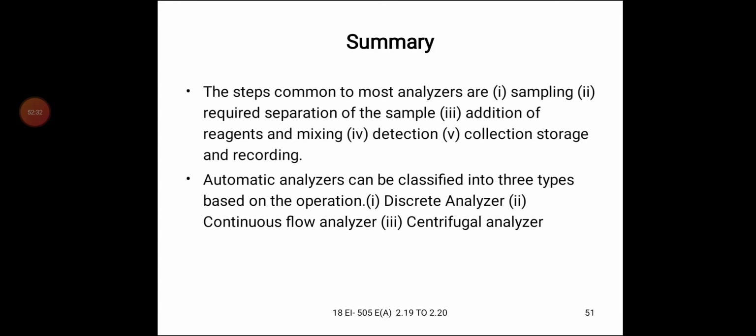The third one is the centrifugal analyzer. The centrifugal analyzer uses centrifugal force, which is a rotational force acting on the rotating disc. Only one detector is readily used to analyze a number of samples.